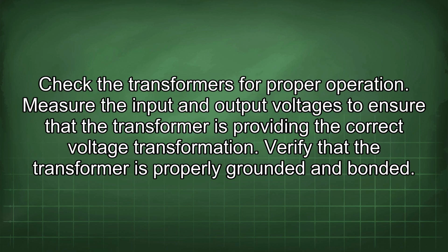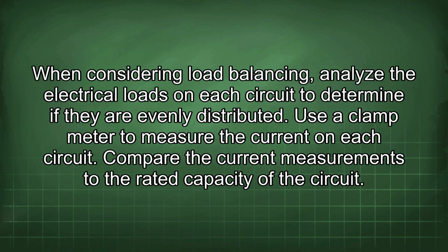Check the transformers for proper operation. Measure the input and output voltages to ensure that the transformer is providing the correct voltage transformation. Verify that the transformer is properly grounded and bonded. When considering load balancing, analyze the electrical loads on each circuit to determine if they are evenly distributed. Use the clamp meter to measure the current on each circuit. Compare the current measurements to the rated capacity of the circuit.